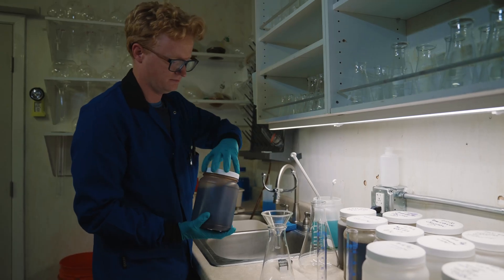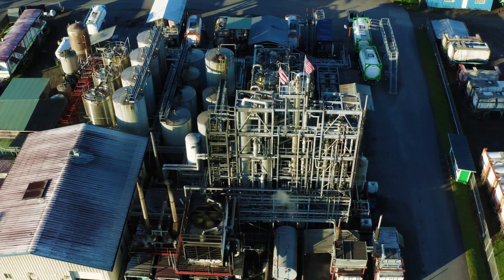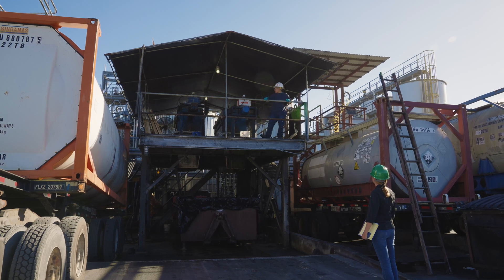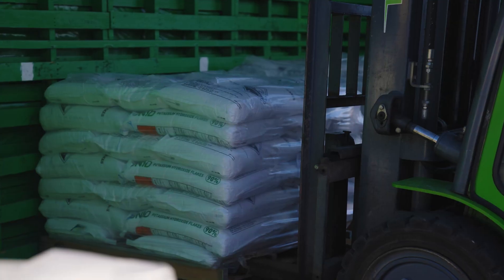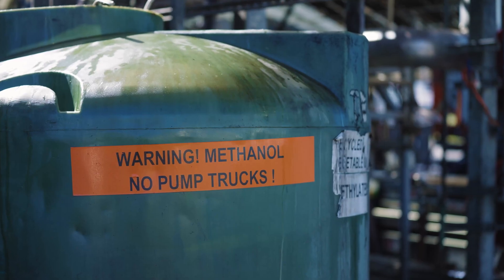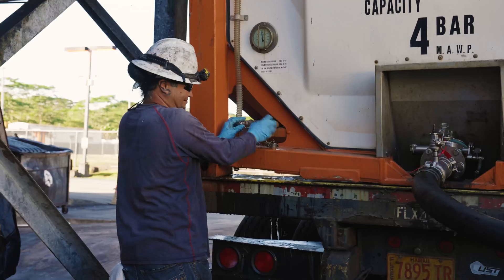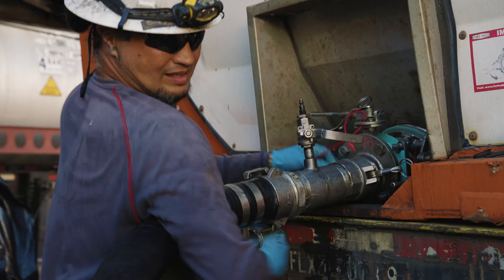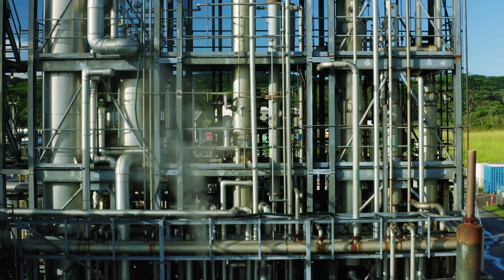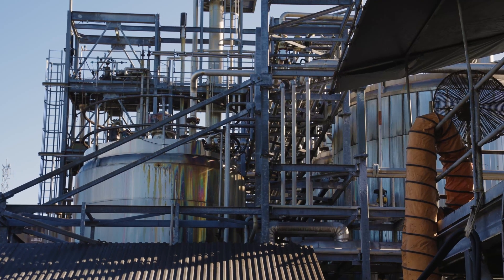Our process is designed to be zero waste and off the grid so we can run on our own fuels. Out of the reactor we have our glycerin and other byproducts. We're able to pull out those salts in the form of potassium sulfate, also known as potash, which is a great fertilizer material. We're also able to pull out the methanol and re-evaporate that into a pure form that we can use again at the beginning of our process. The crude glycerin goes into waste water processing facilities around the world. We use our distillation column bottoms to run our boilers for heat and steam, so we make our own fuel to provide our own heat.